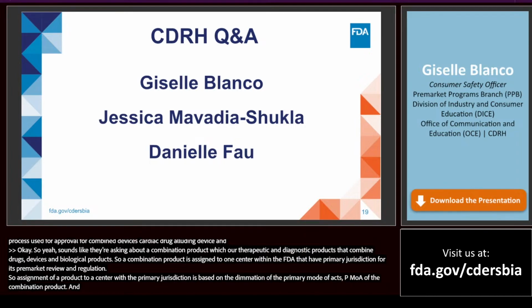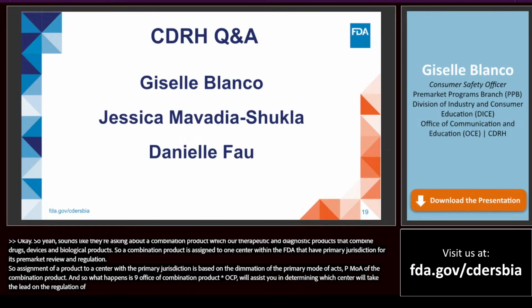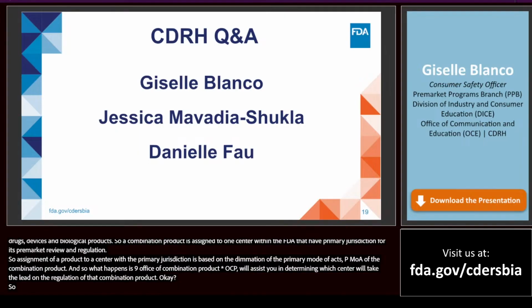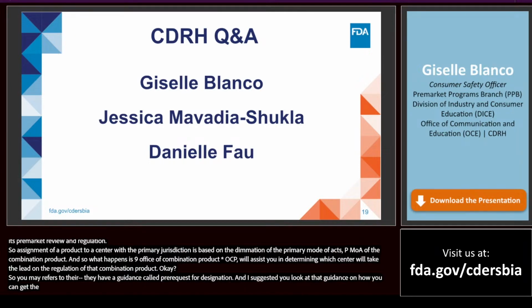Assignment of a product to a center with the primary jurisdiction, also called the lead center, is based on the determination of the primary mode of action, PMOA, of the combination product. The Office of Combination Products, OCP, will assist you in determining which center will take the lead on the regulation of that combination product. You may refer to their guidance called Pre-Request for Designation, and I suggest you look up that guidance on how you can get the OCP office to help you with your determination. They also have an FAQ webpage, so I suggest you check out their webpage as well. That is the Office of Combination Products.